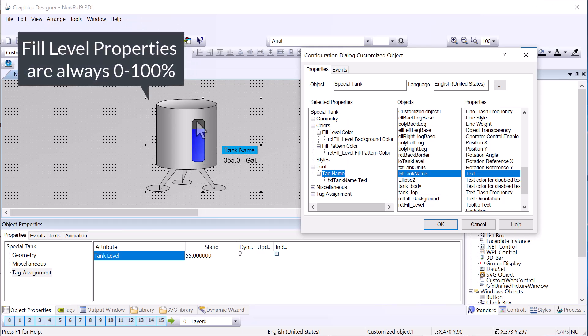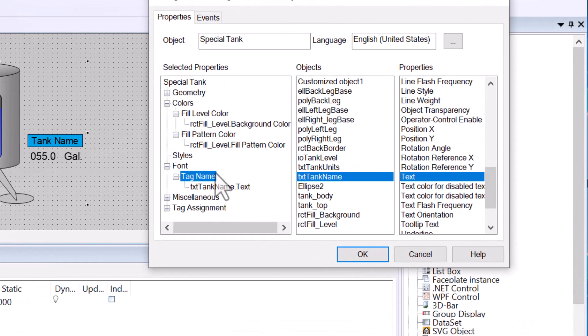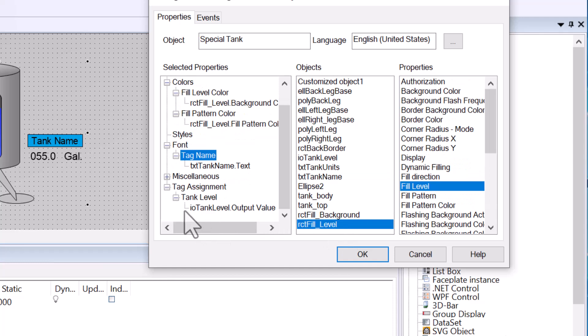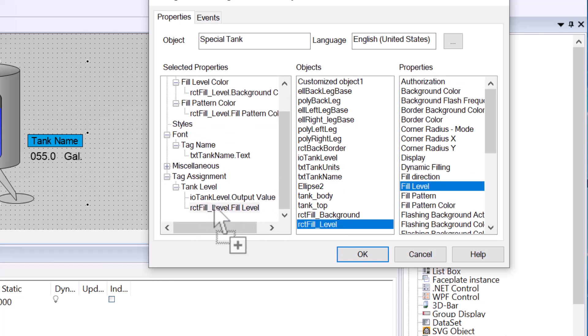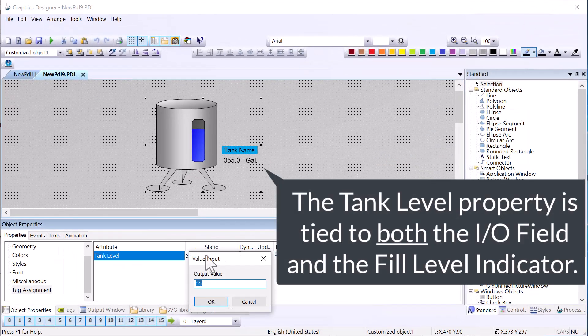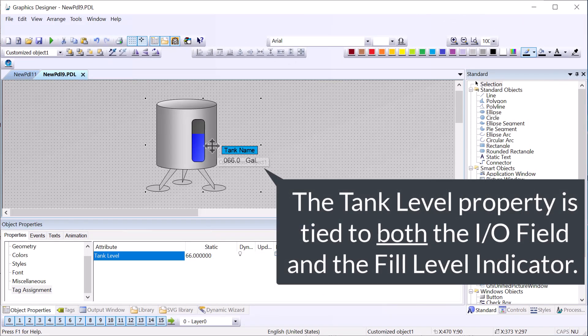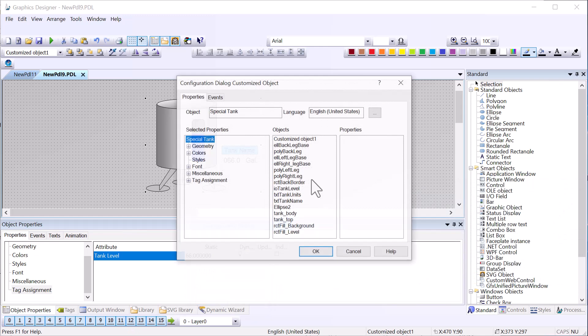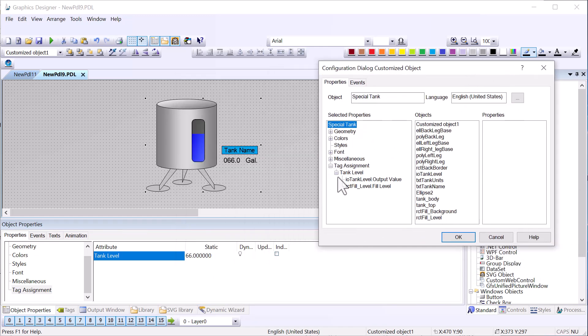Now for the fill level — this will be 0 to 100 because fill is always by percentage, but it's going to be the same value as what's on the IO field. So I'll find our Fill property and assign it to this exact same Tank Level property. What that's going to do — and I'll click OK to show you — is now since both properties are tied to this one, both my fill level and my output value change when I change this one property. As long as the data indicates the same thing, you can put it under the same property.